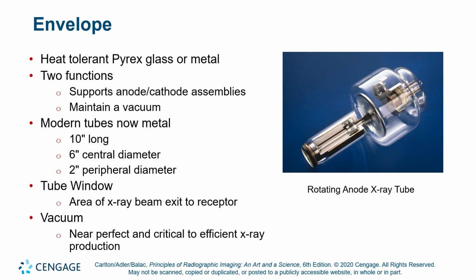Okay, right? The tube window is the area of the intended exit of the X-ray beam. Now remember, the X-ray beam actually spreads in all directions, okay? But the tube window is facing toward the collimator box and the aperture to the tube housing. That's what's special about the tube window. In glass envelopes, the tube window was the thinnest portion of the glass envelope. I don't know how they do it with the modern sheet metal envelopes, whether they pound it thinner right there at the tube window or they leave it the same thickness all the way around. Okay.